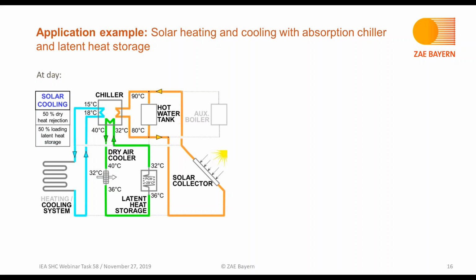At day, the system is driven by a solar thermal collector providing heat at 90 degrees C to a thermally driven absorption chiller, which in turn provides cold at 15 degrees C to a cooling system. And to keep this process running, heat needs to be rejected.